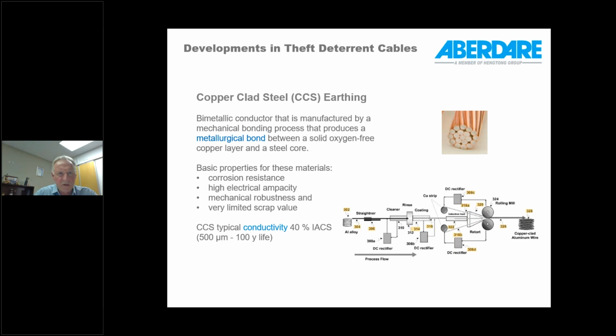So just a little bit more detail on copper-clad steel earthing. There's a thin layer of copper which is applied over a steel substrate, and this kind of system relies on a metallurgical bond between the two metals, and that's the reason why it can't be separated mechanically. You have to use a chemical process if you were to try and separate the two metals.